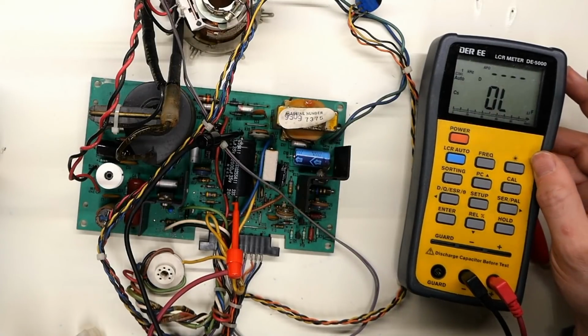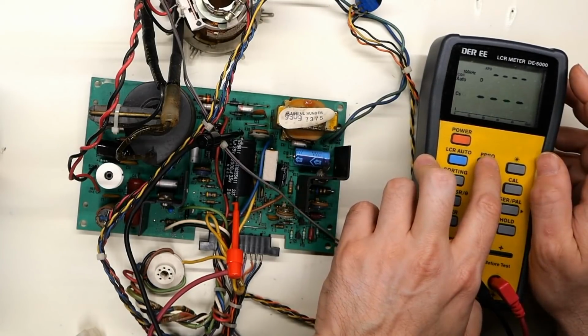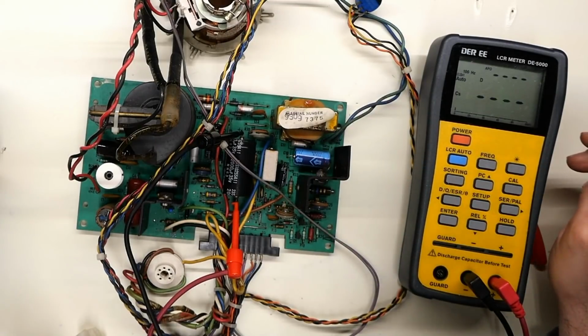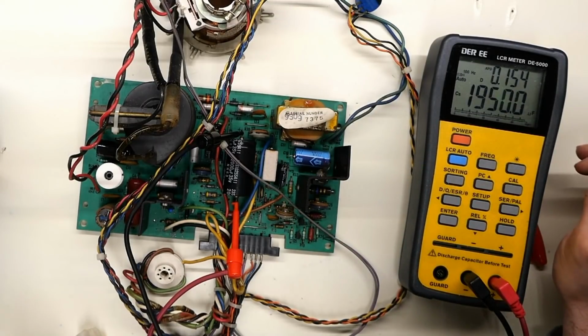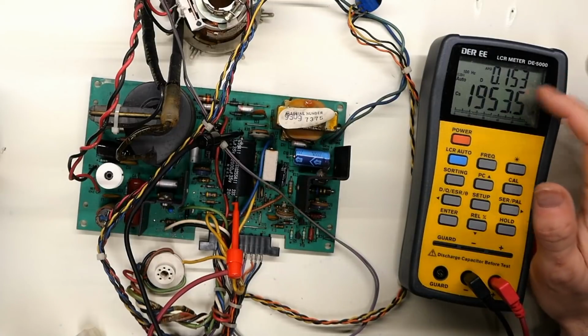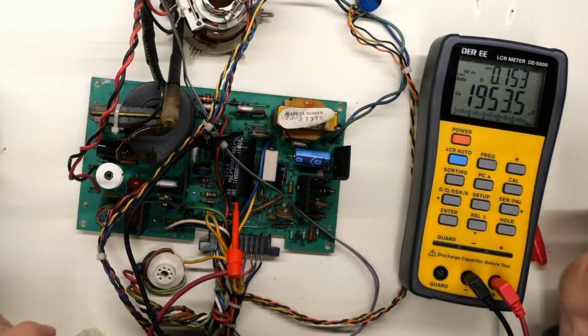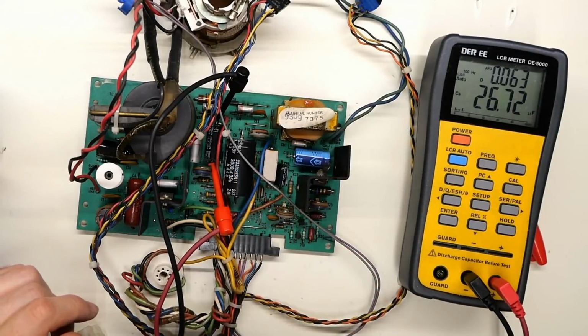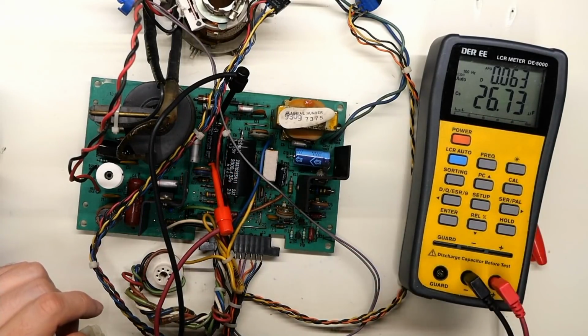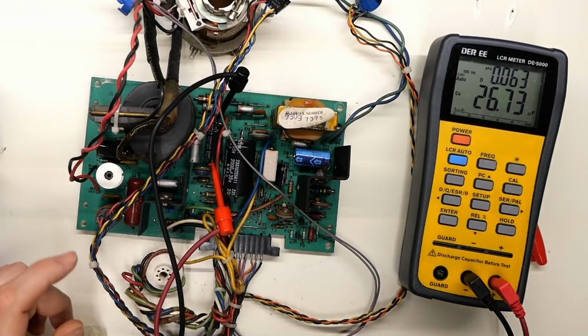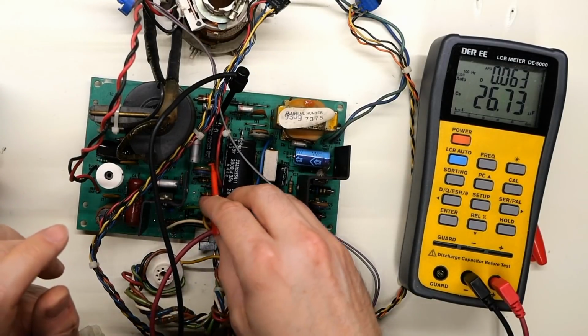It just says OL. I'm going to change the frequency to 100 hertz, see if that works better. There we go, about a little under 2000, and 0.15 is the D, which is fine. Next up, 22 microfarad - we're getting 26 at a D of 0.063, which is quite low, so that one is fine.